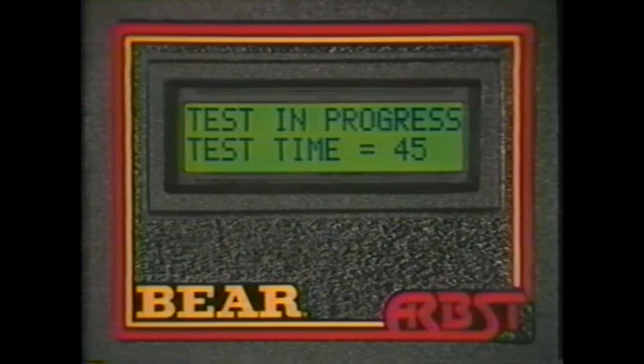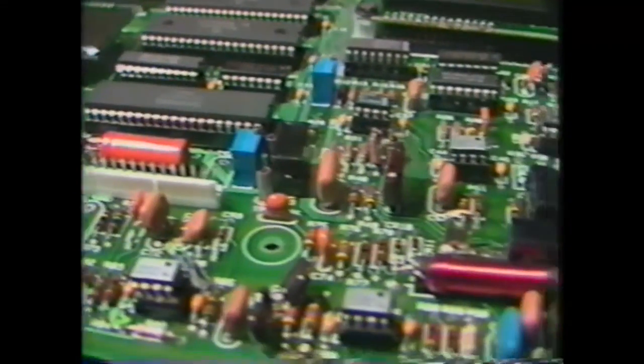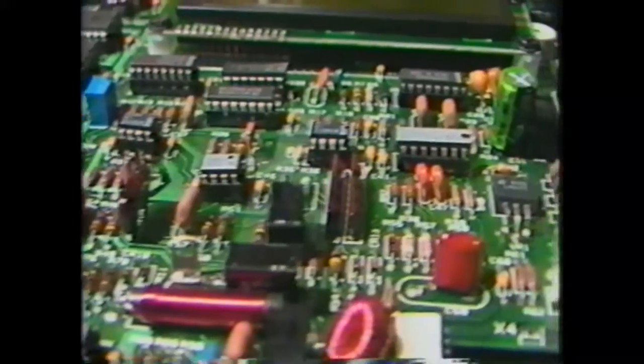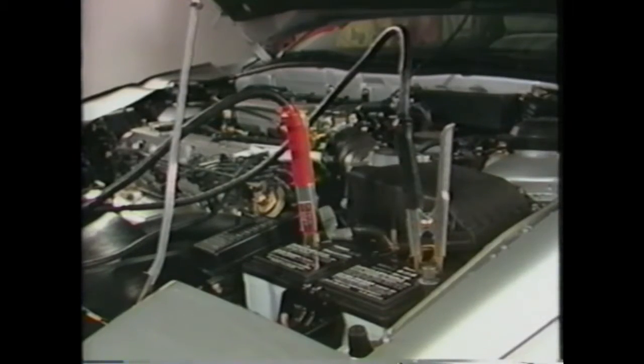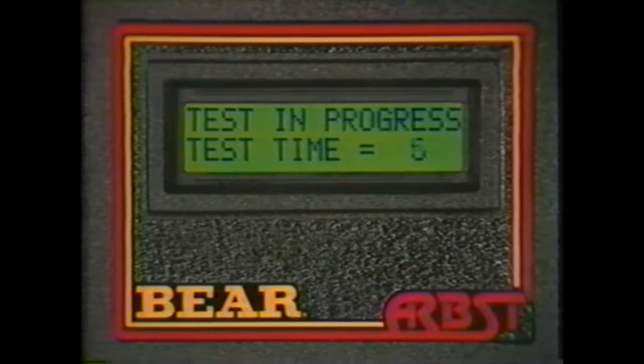The display says Test in Progress, and after a short pause, a counter starts from 50 seconds. During that 50 seconds, ARBST applies a load to the battery, releases it, then applies it again. You can hear a solenoid click when the load is applied and released. While the test is being run, the ARBST computer is gathering and calculating a number of battery parameters in order to determine the overall condition of the battery. After 50 seconds, the test is complete, and the main display shows the test result.